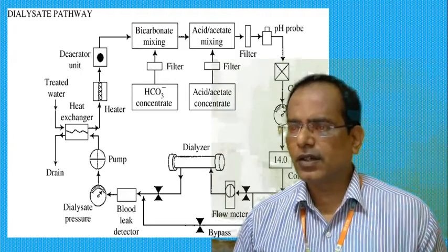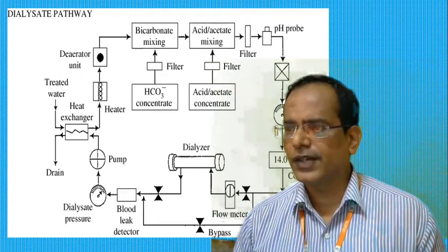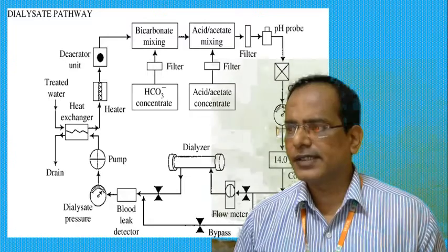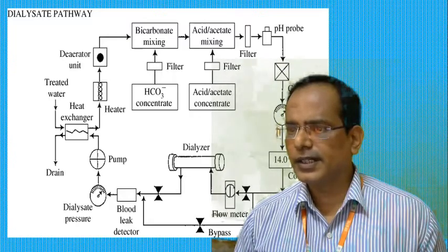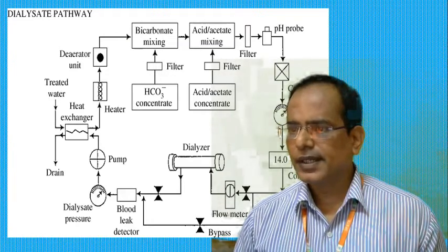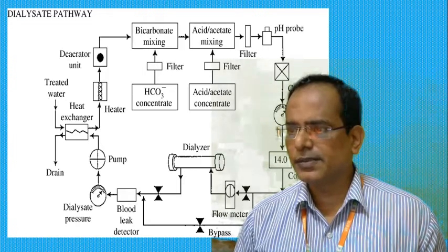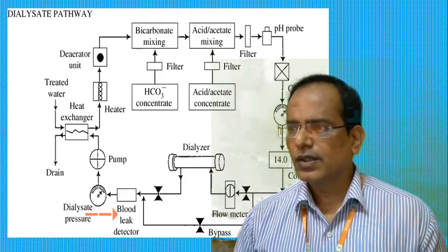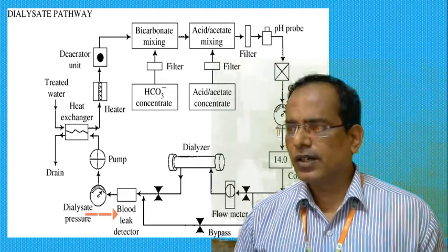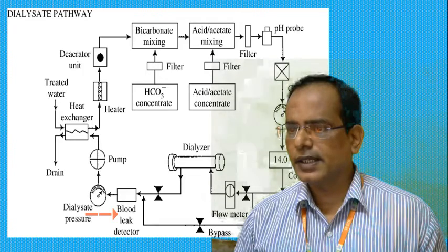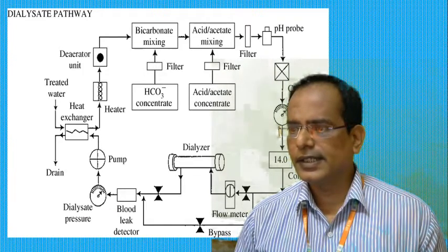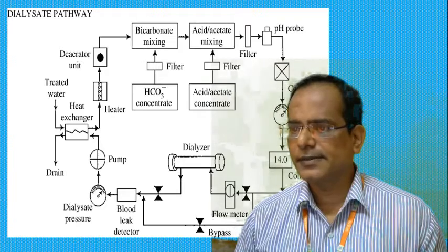The concentration of electrolytes in the dialysate is also monitored by an electronic instrument, because the solute is made up of electrolytes. The overall concentration of these in the dialysate is determined by impedance techniques.